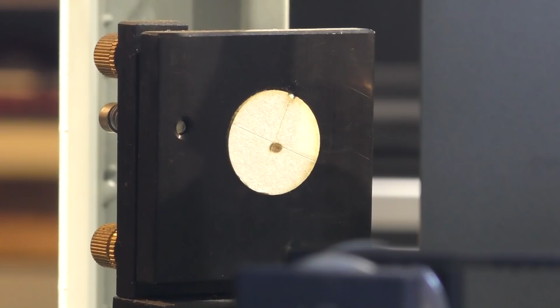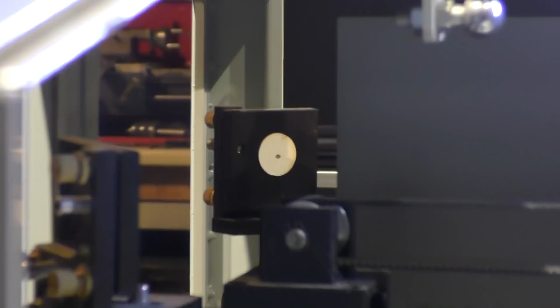So I've got my power set to 15%, and we'll just give it a very quick pulse. There we go. Now, it's low. Am I worried? No. Is it central, left and right? Yes. Why am I not worried about it being a little bit low? We've got a mirror that is round, but the laser beam is not looking at the mirror like that. The laser beam is looking at the mirror like this, at 45 degrees. So the height has not changed, but the width has. So I've got to be fairly accurate on the horizontal dimension to make sure that it stays in the centre of the available oval shape that the laser is looking at. We're looking at a circular shape, but that's not the same for the laser. So a couple of millimetres up or down from centre is not an issue. I'm going to leave that mirror as it is.